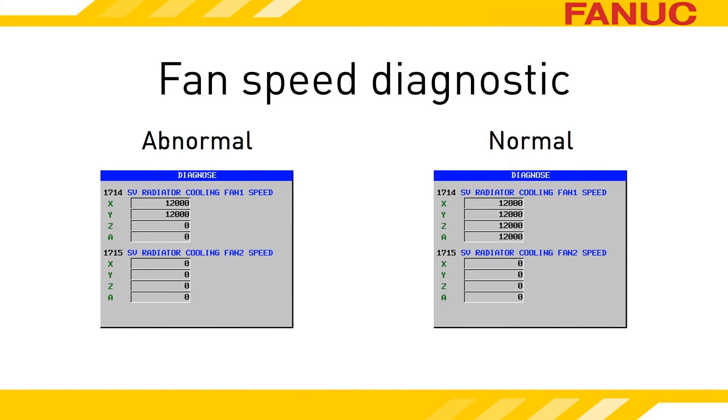The latest series of amplifiers have a diagnostic that shows you the fan speed. This comes in handy if the fan is not turning. CNC Diagnostic 1714 reports the RPM reading of the fan. Diagnostic 1715 is for larger amplifiers that have two external fans. If you don't have those diagnostics on your CNC, it just means your amplifiers are older models.